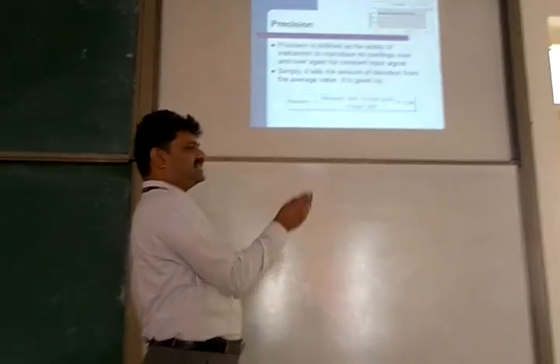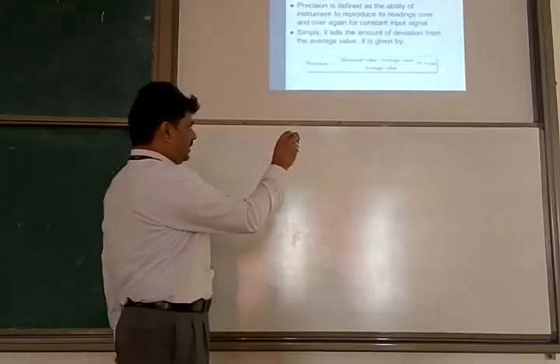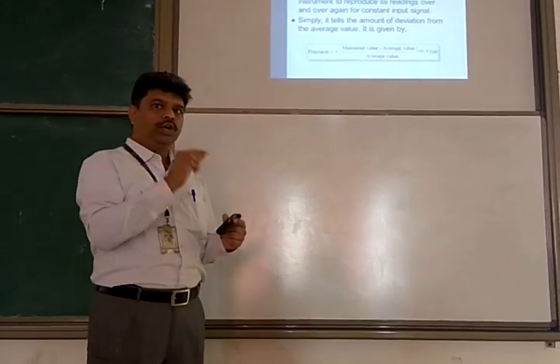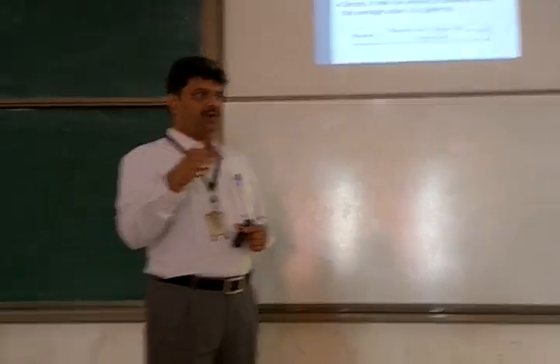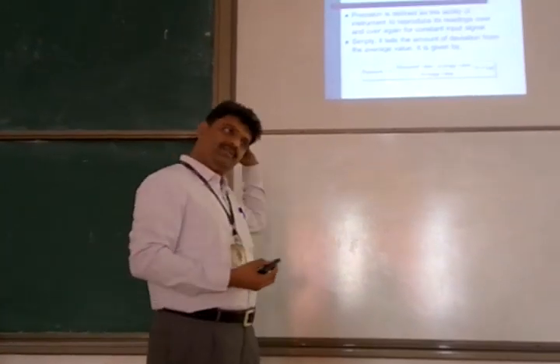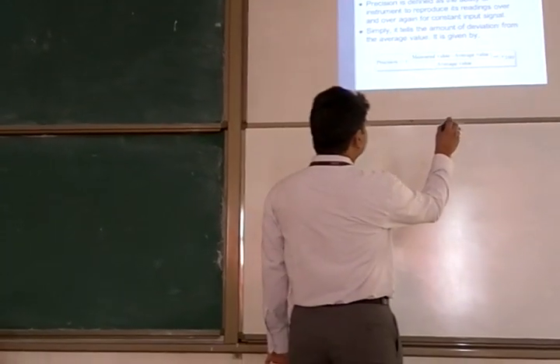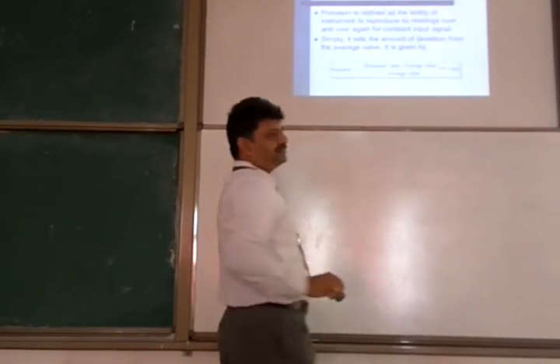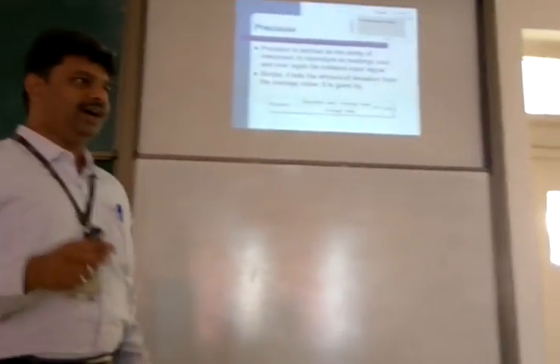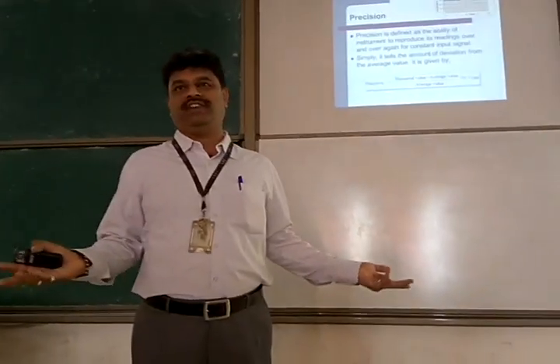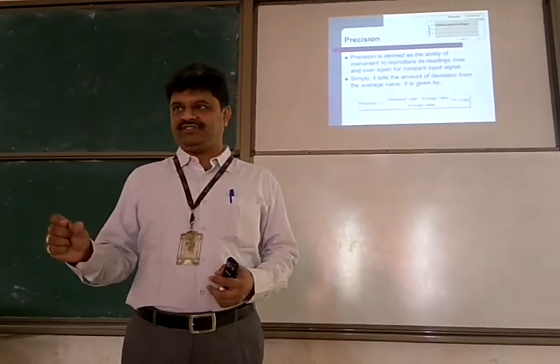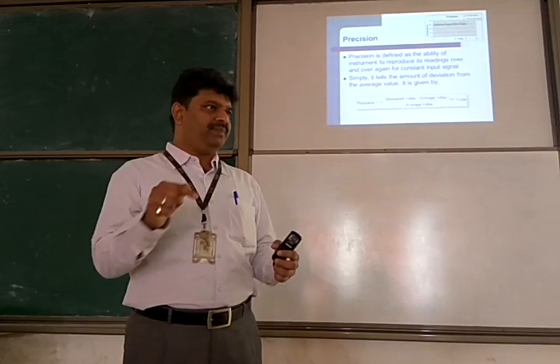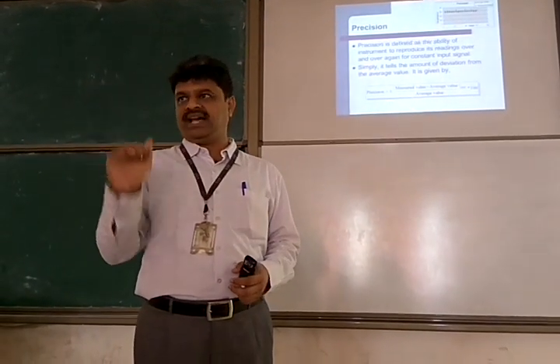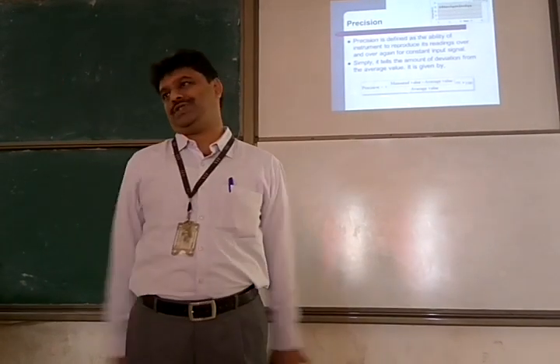So the plus or minus sign has the same significance as I explained for accuracy. You have to put the percentage sign, plus or minus 2%. If you don't put that percentage, again it is wrong. I explained the reason when we discussed accuracy. And here there is a max. Normally students ignore this, and in the examination again they make a mistake. They compute precision for each reading and then simply say there are 6 different precisions. No. One instrument can have only one precision. It cannot have 10 different readings and 10 different precisions. So you need multiple readings. Take the average of those. Each reading you subtract from the average. Take the biggest difference, divide by the average, into 100, and the plus or minus percentage will give you precision.